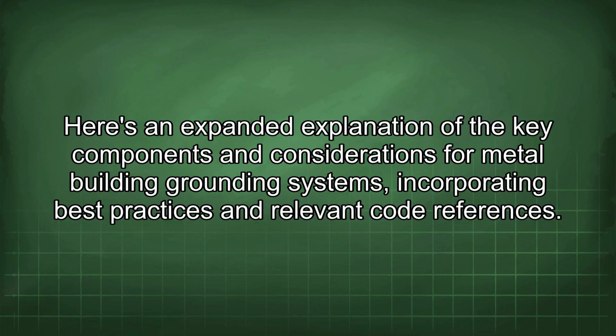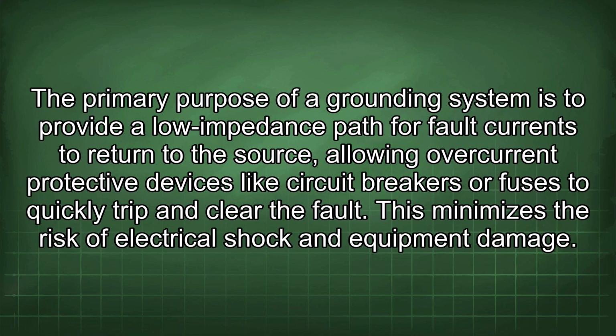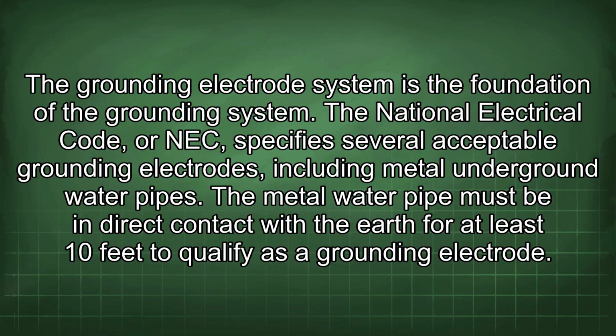The primary purpose of a grounding system is to provide a low impedance path for fault currents to return to the source, allowing overcurrent protective devices like circuit breakers or fuses to quickly trip and clear the fault. This minimizes the risk of electrical shock and equipment damage. The grounding electrode system is the foundation of the grounding system. The National Electrical Code, or NEC, specifies several acceptable grounding electrodes, including metal underground water pipes.